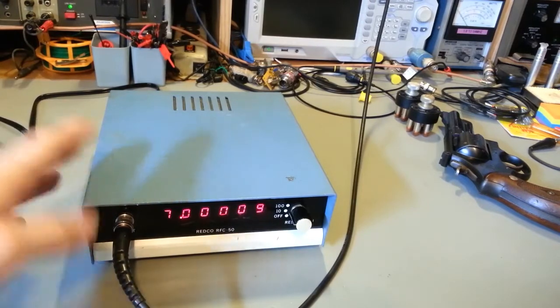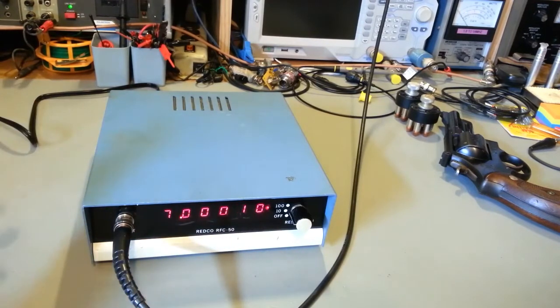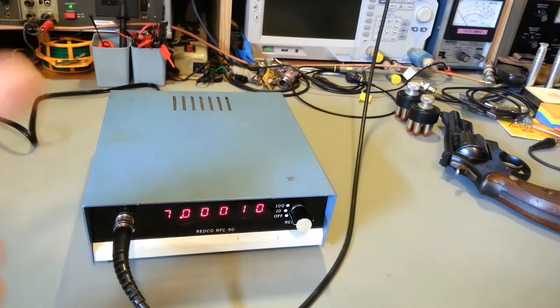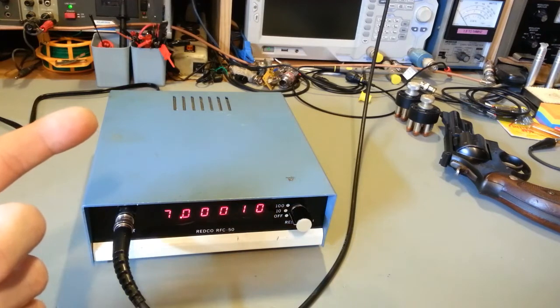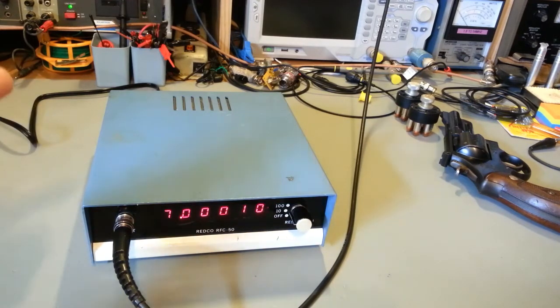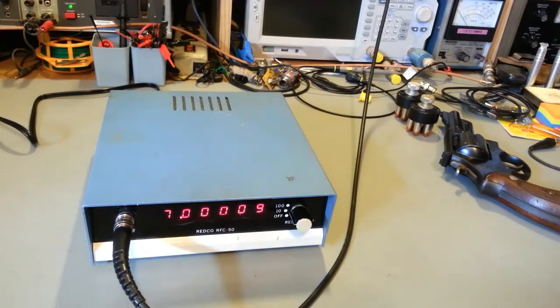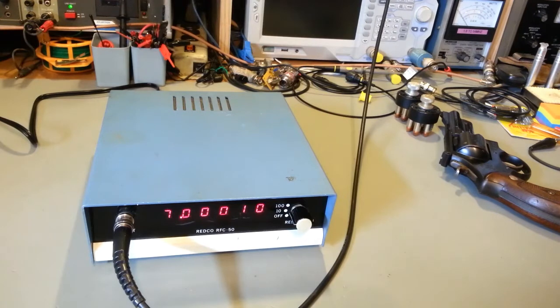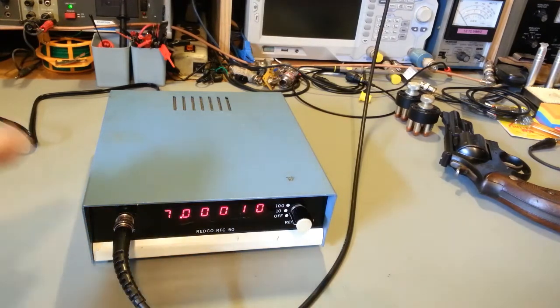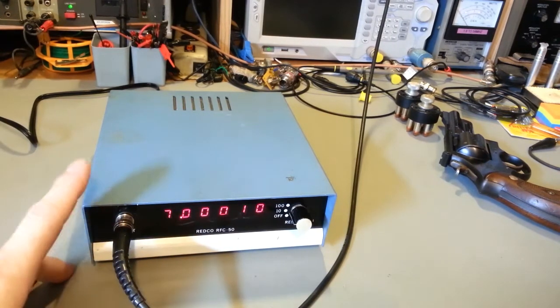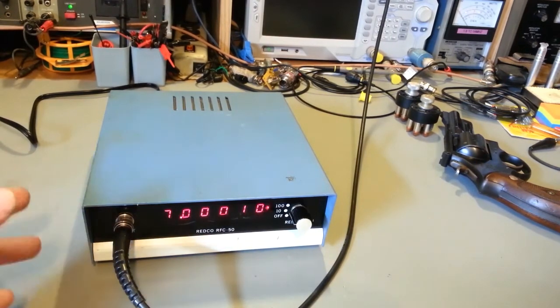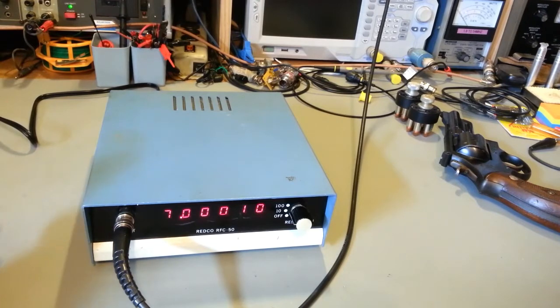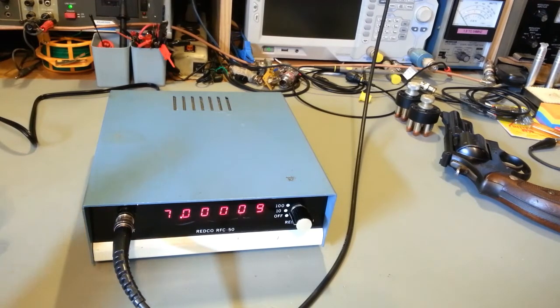To calibrate this, for starters you should have something with a fairly accurate frequency going into it. That's why I'm using the signal generator up there. That is referenced to a GPS disciplined oscillator, so I know that thing is dead on frequency. It's disciplined to the GPS satellites hovering over our heads. But you don't really need something that accurate for this.